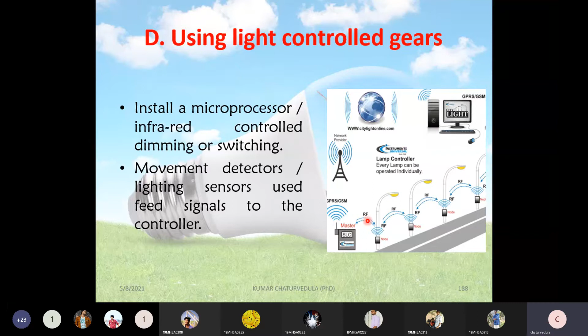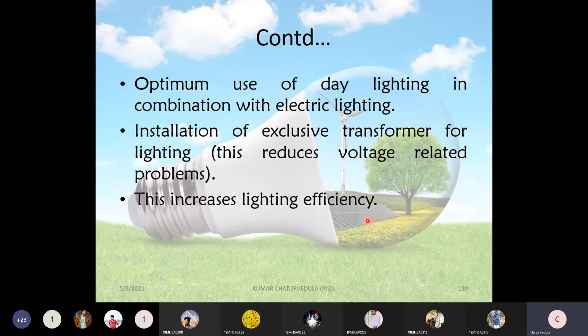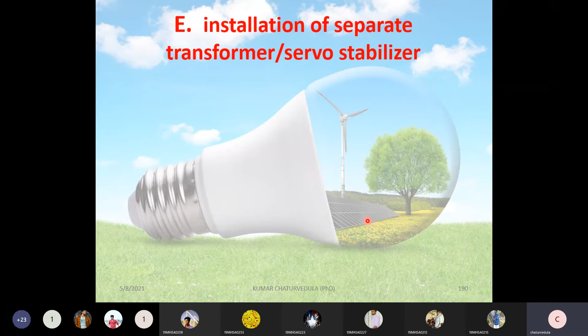So optimum usage of daylighting is essential. Then installation of an exclusive transformer to reduce voltage stress on the lighting system. If required, you can install a transformer dedicated only for the lighting, which improves the lighting efficiency. So installation of a separate transformer or servo stabilizer. The point in the previous item is going to be continued here.